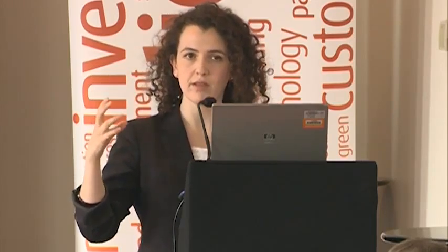However, at the same time, and again, this is why March Grid became such an interesting and good example for us, as Satiris mentioned, in the March Grid the constraint is essentially the transformers. And there is a network plan that could imply upgrading those transformers. The cost of that is about £4.1 million. And essentially what we thought, well, if you could compare the cost of paying for that reinforcement in a, again, pro rata way, you could eventually hit that point where those two lines cross. So the line going down essentially means the more megawatts I connect, the less expensive it would be to pay for the reinforcement if everyone were to pay for it equally.